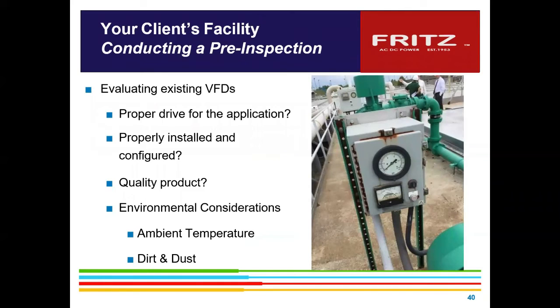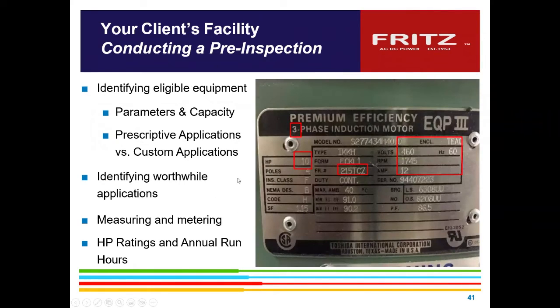So again, where it needs to be installed, the proper type of enclosures, do they have to be mounted away in an area? You've got to be worried about the ambient temperatures that they're running in, and dirt and dust, so that we get a proper application. What we recommend is also to take pictures of your nameplates on your motors, so that you can determine exactly what you've got going, and we can also determine more about the compatibility of the motor.